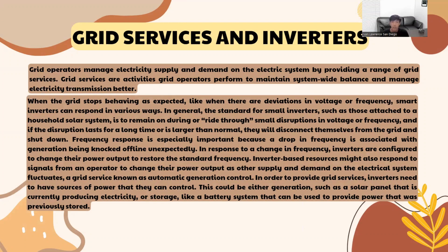Inverter-based resources might also respond to signals from an operator to change their power output as other supply and demand on the electrical system fluctuates. A grid service known as automatic generation control. In order to provide grid services, inverters need to have sources of power that they control. They could be either generation, such as a solar panel that is currently producing electricity, or storage, like a battery system that can be used to provide power that was previously stored.